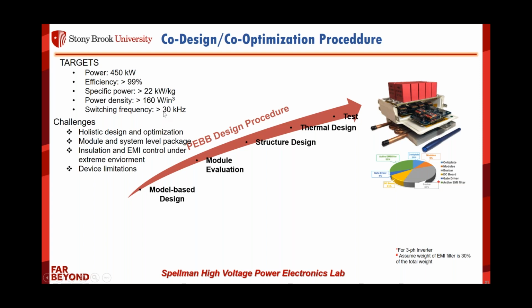The reason why we want to switch at a much higher frequency than existing motor drives is because the load, which is the high-speed, high-density motor, usually comes with much less inductance. So you need to have a high switching frequency in order to reduce the harmonic influence to the motor itself.